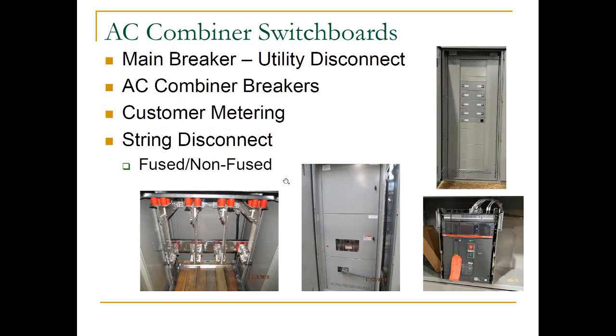If they want a draw-out circuit breaker, if they want a fixed mount circuit breaker as that main disconnect, if they want a fused visible blade disconnect switch, we can build that. So we can tailor these switchboards with the components internal to them. Essentially, however, you as the end users, or the end users that you are working with, need to for the installation across the US.